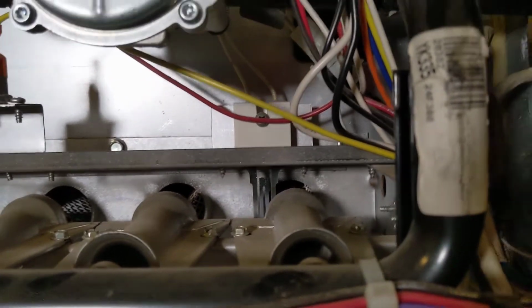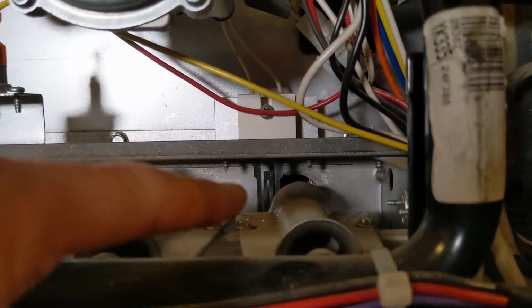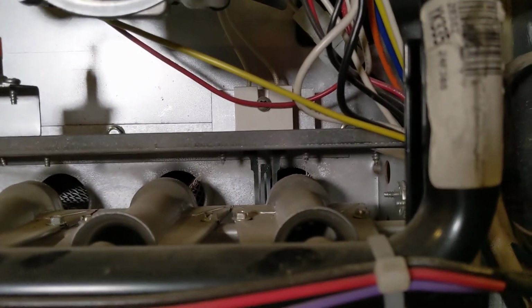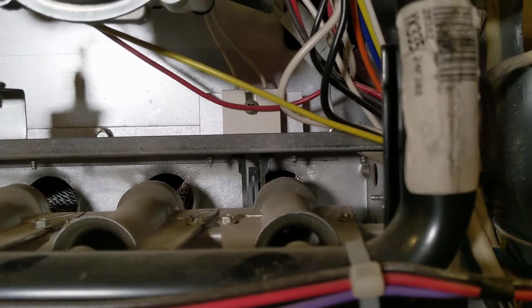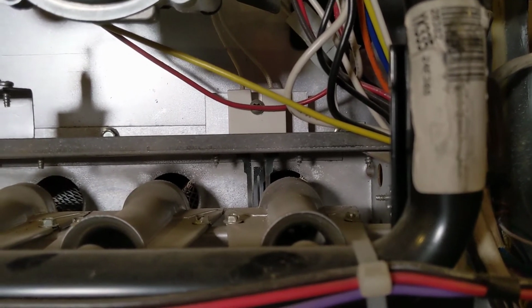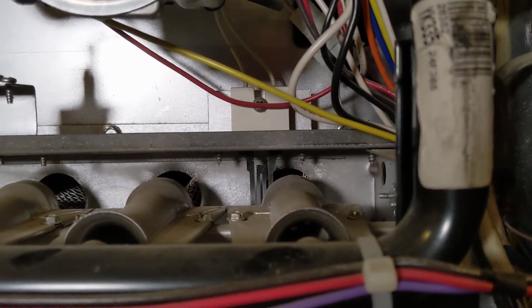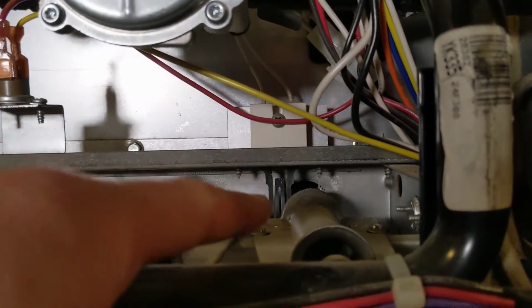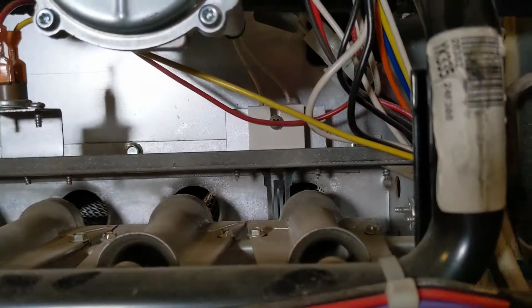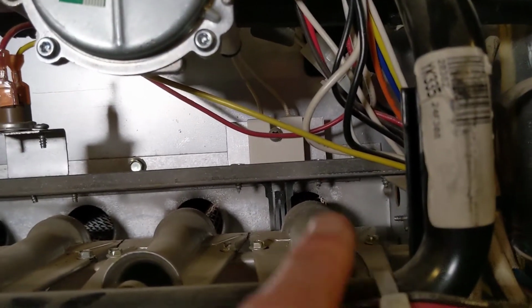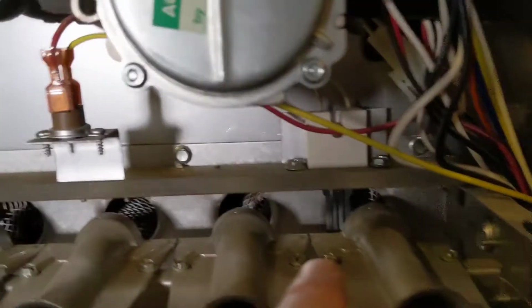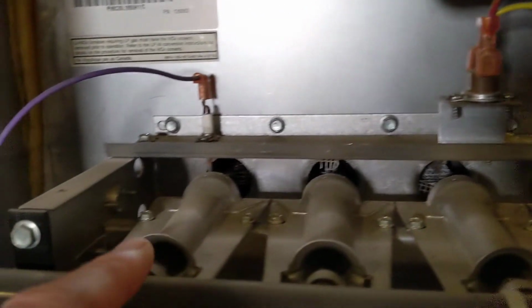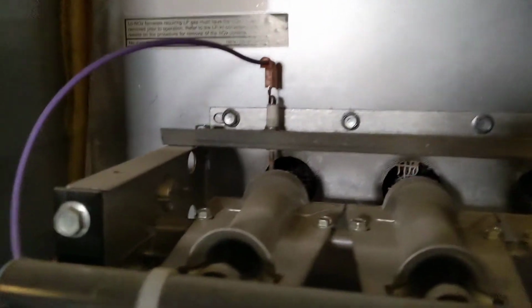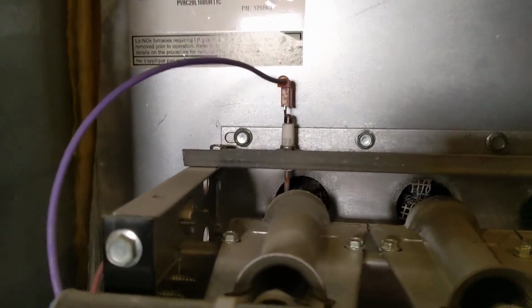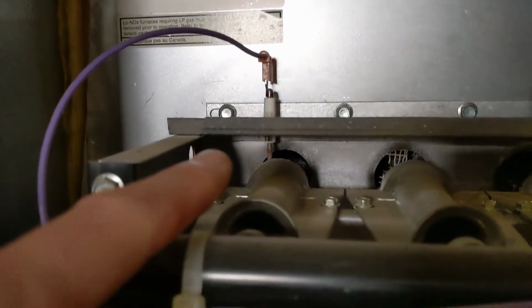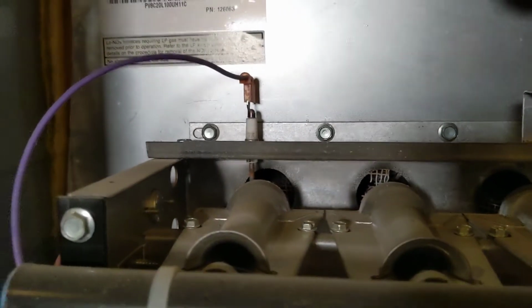Another version of that igniter is a tungsten glowing type, where it heats up. Another type, you'll hear a ticking sound, kind of like one of those gas grills, where it creates an electrical spark. But either way, you should see that thing glow or hear a ticking sound, and that should spark the gas and ignite it. Once it ignites on the first burner, that flame will spread in line to all the other burners. And the last burner will almost always have this guy right here. There's a little metal rod going down there, and that's called a flame sensor.